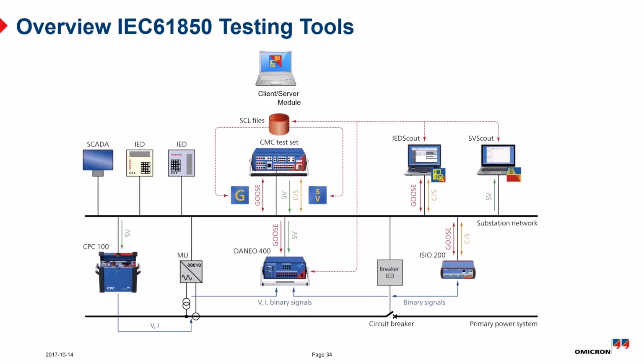And of course, because it's an Ethernet-based solution, we've got some other tools here. We've got IED Scout, which is basically a software that sniffs the network. You can look at any device on the network and see what's happening on the network, what GOOSE messages are present, what client server communication is done, and so forth. The SV Scout is another software. We have a software that will measure sample value streams, so you can actually plug into the network, subscribe to a sample value stream, and see a calculated RMS value. This allows you to troubleshoot these networks.